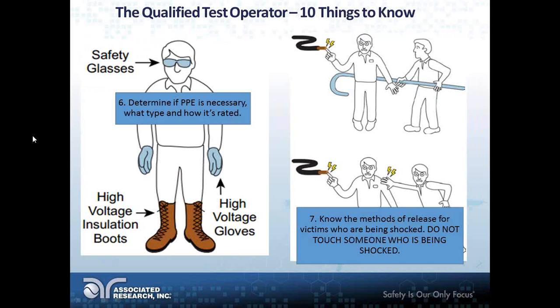Determine if PPE is necessary. Remember that safety approach, or that prohibited approach distance I was talking about, that 2 feet 2 inches? If you're going to get within that range, and it's between 750 and 15,000 volts, which if you're running a high pot test, it most likely is in that range, use your PPE, know how it's rated, know how to use it. So the guy they show here, he's wearing high voltage gloves, he's got on safety glasses, and he's wearing his handy-dandy high voltage insulation boots as well, which basically isolates you from ground potential. So not a very attractive path if you have on insulation or isolation boots.